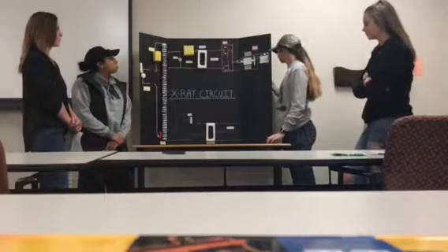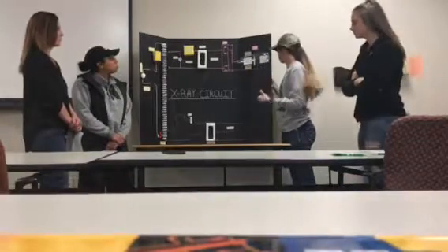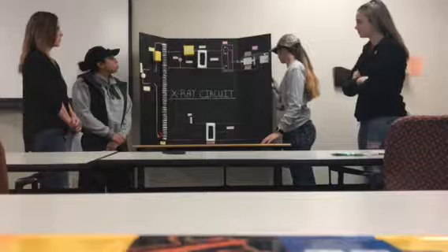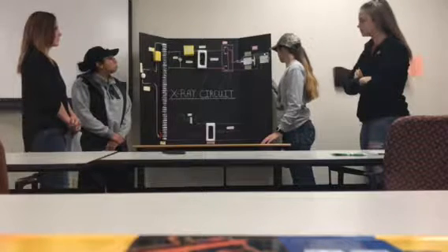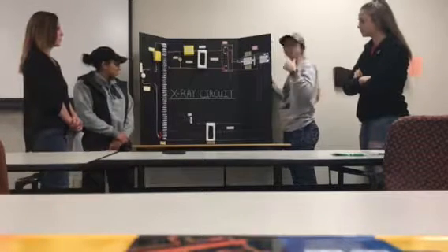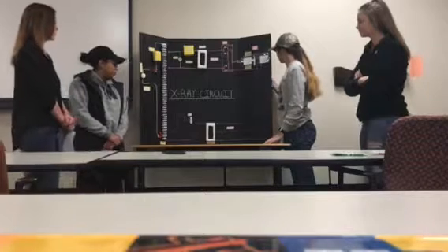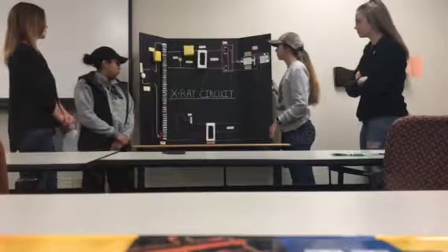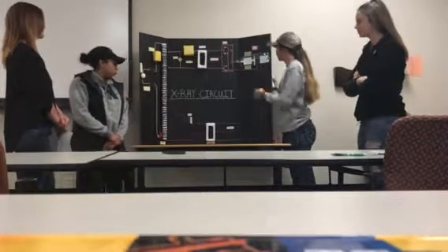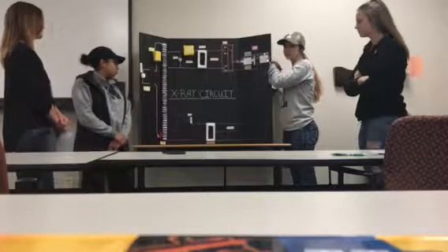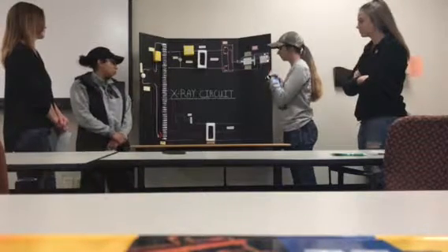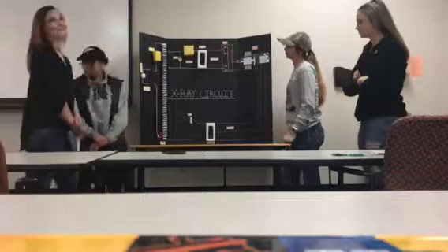The rotating anode is turned using an induction motor to operate through the mutual induction that Bree was talking about earlier. And the cathode provides the source of electrons needed for X-ray production, and it also consists of the focus cup and the filaments, which leads into the filament circuit.